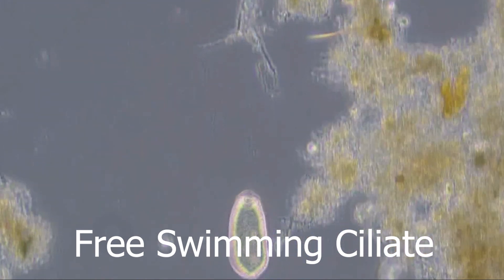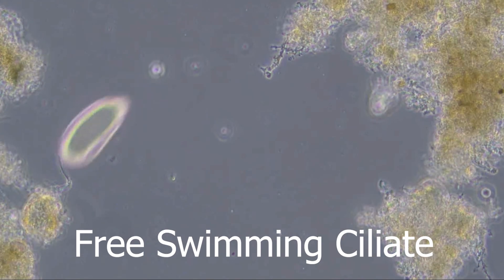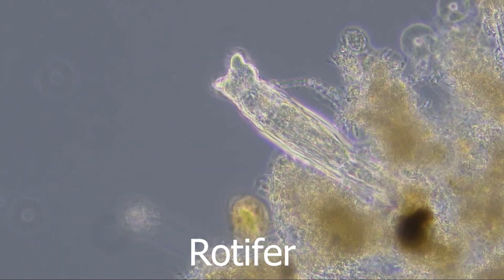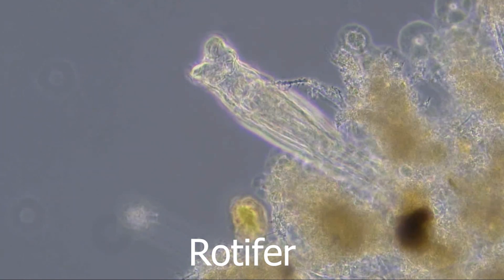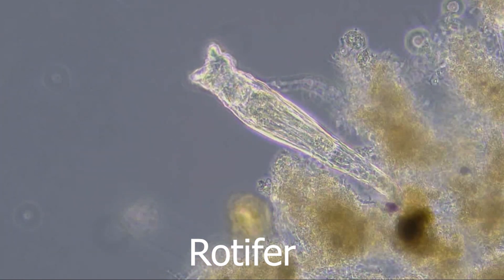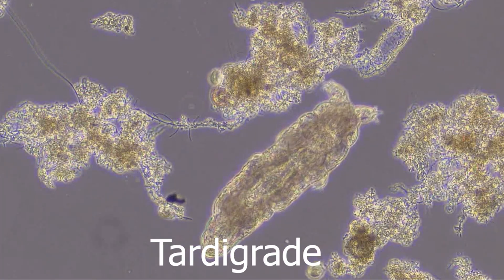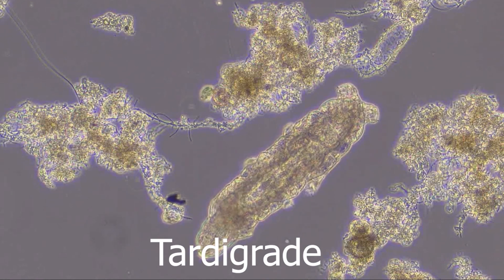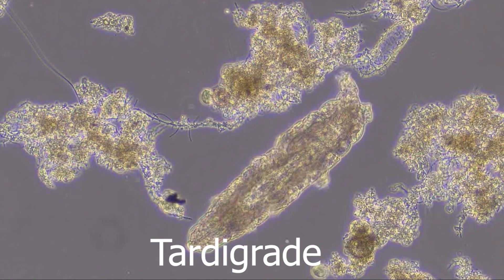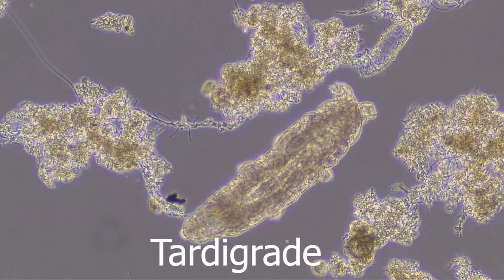These microorganisms include bacteria, protozoa, and metazoa. They naturally occur in freshwater, but they are concentrated in wastewater. They consume biodegradable organic contaminants such as sugars, fats, and carbohydrates, then bind less soluble fractions into floc. This system is designed to substantially degrade biological content of sewage derived from human waste, food waste, soaps, and detergent. This part of the process takes about four to six hours to complete.